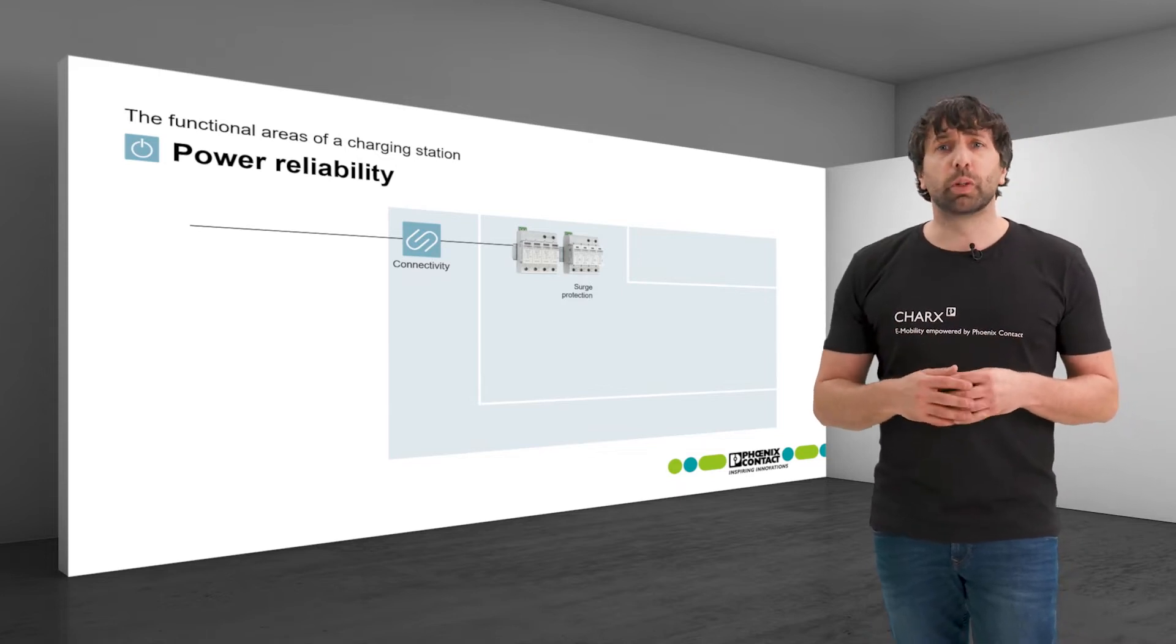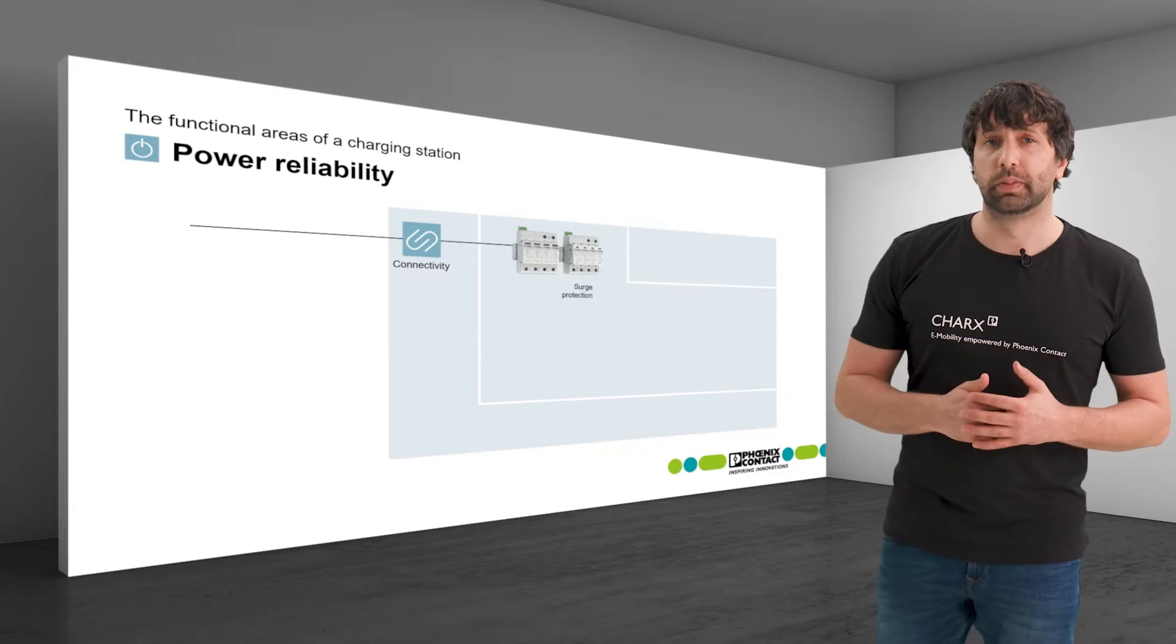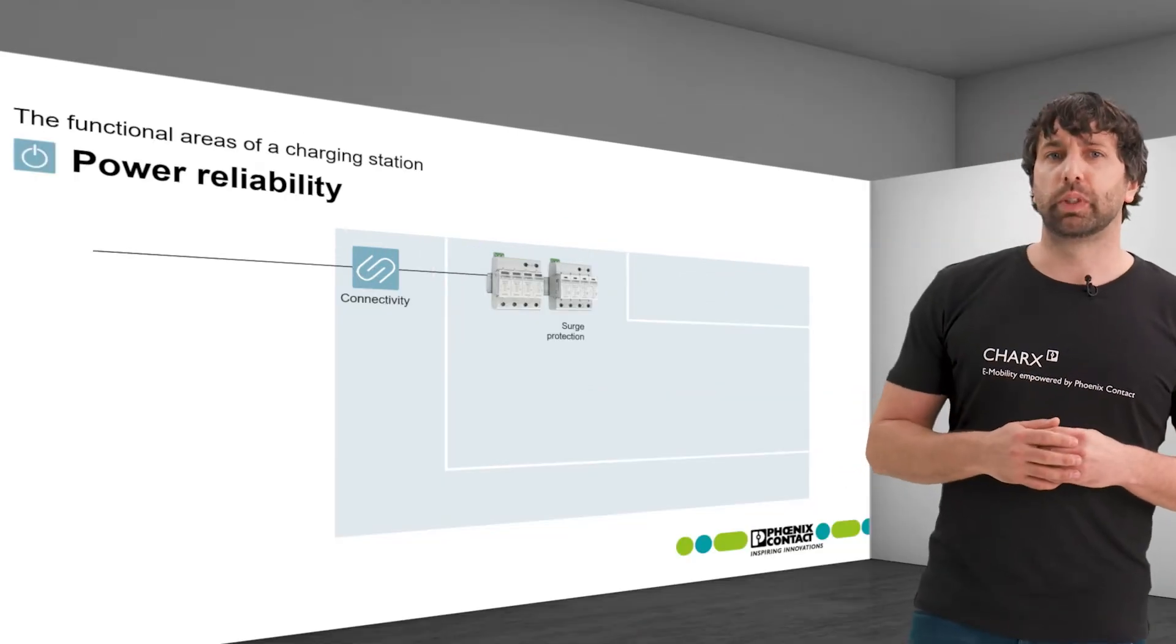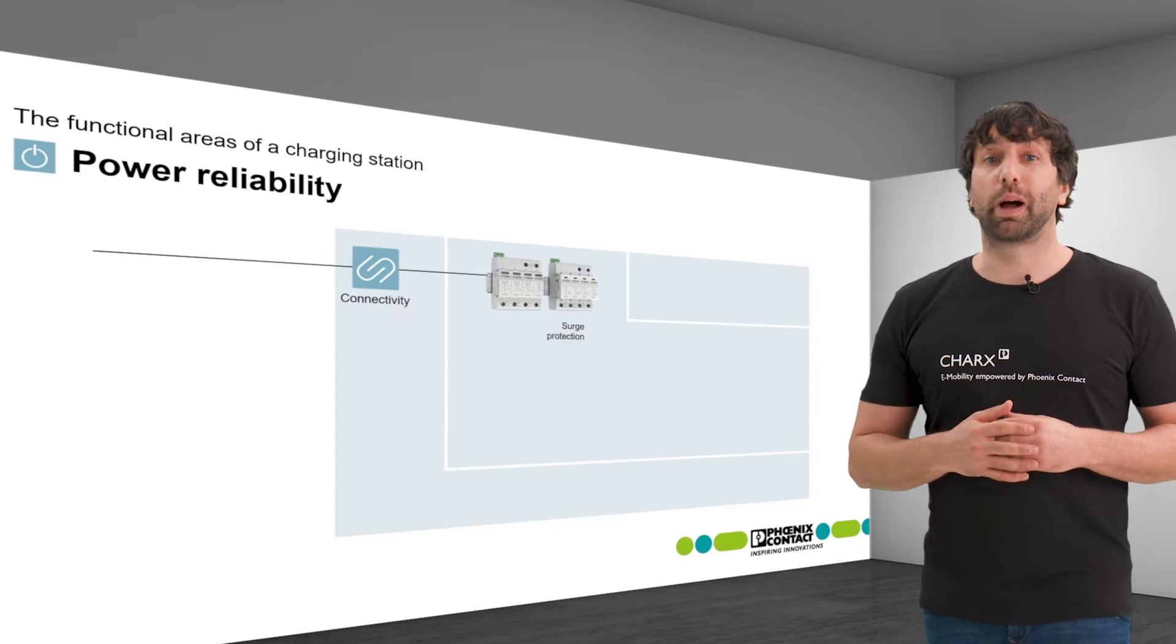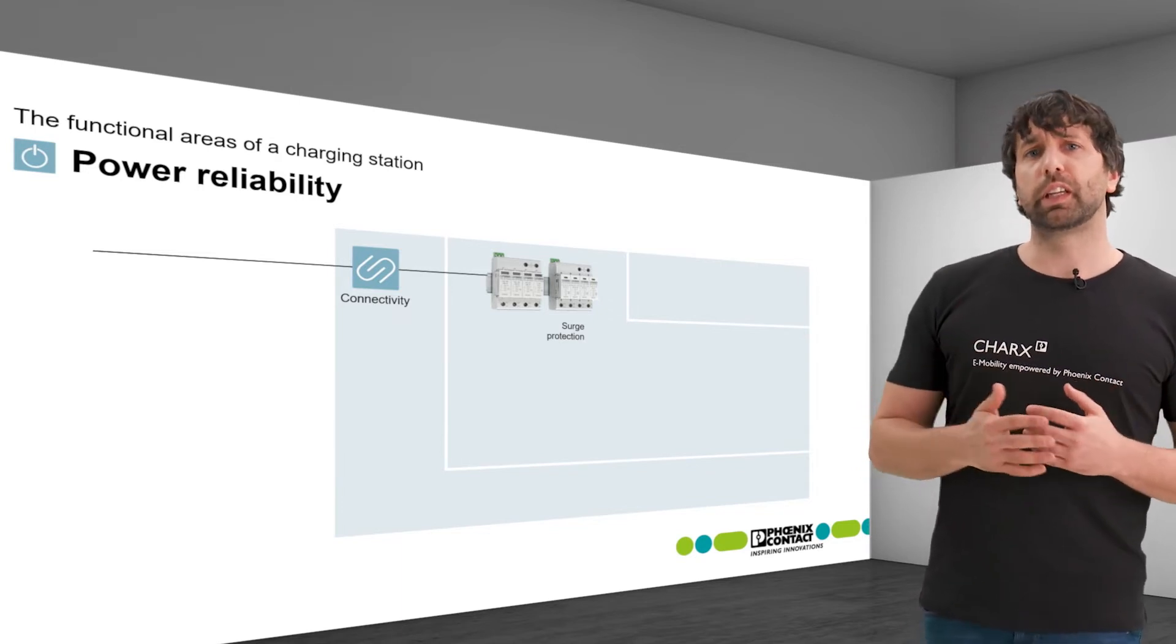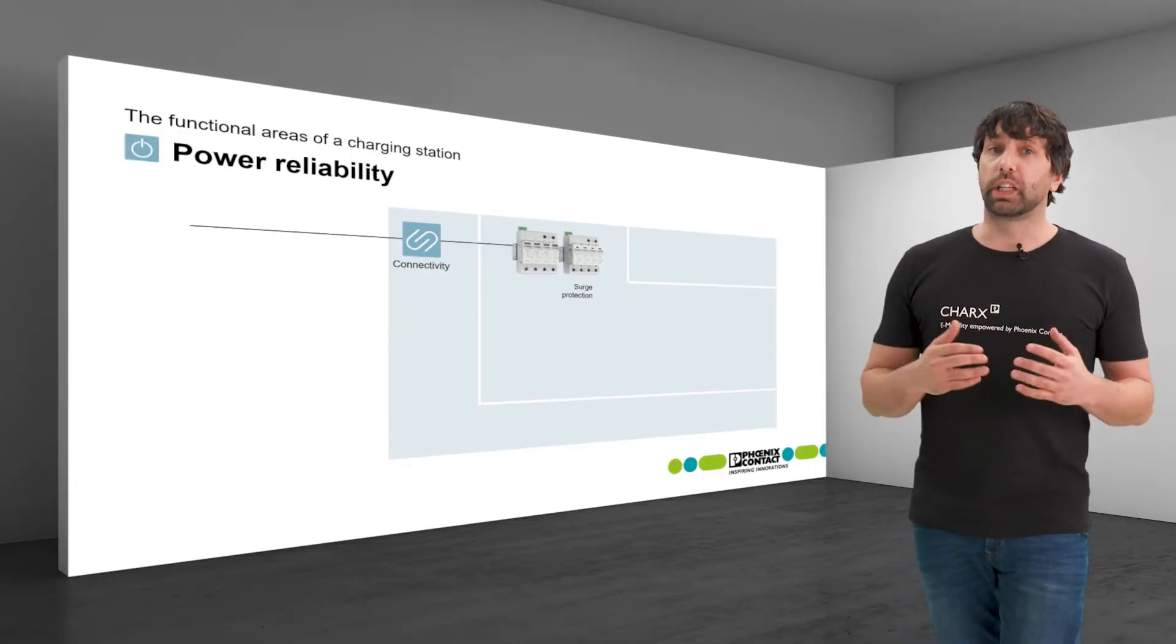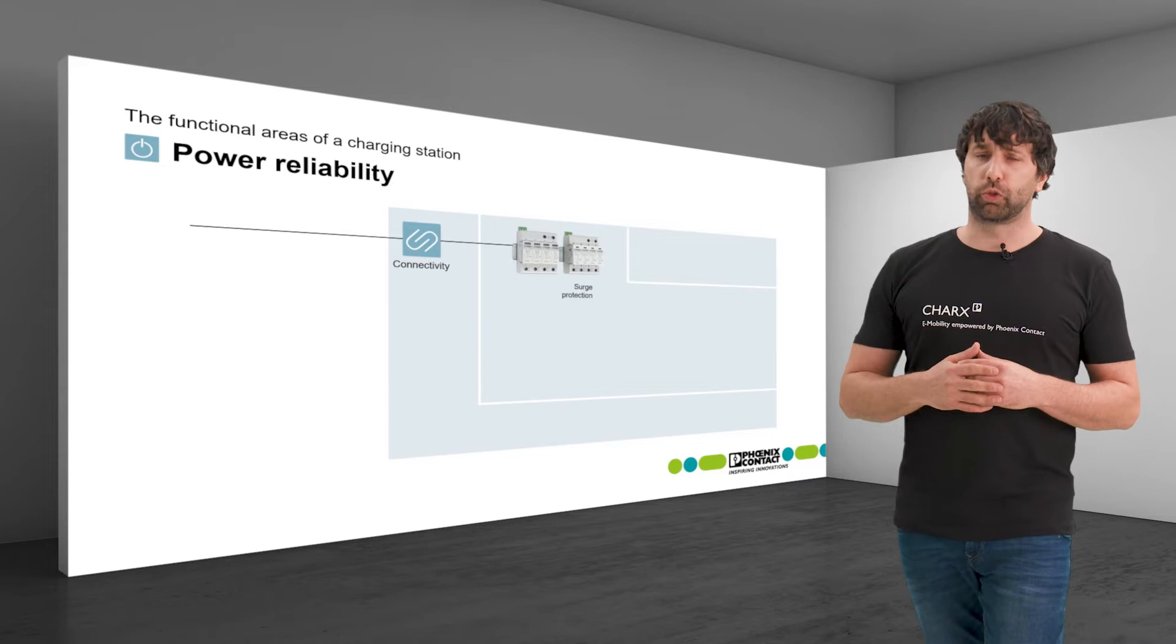Thanks to its pluggable modules it is quick and easy to maintain in case of an error. Combined lightning current and surge protective devices, so-called combined type 1 and 2 arrestors, can disconnect up to 50 kA. Simple type 2 arrestors up to 40 kA are sufficient for home chargers.